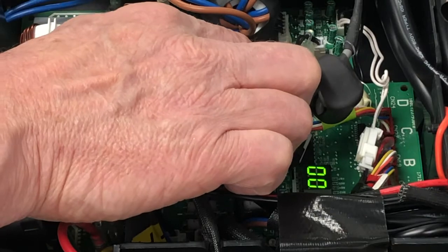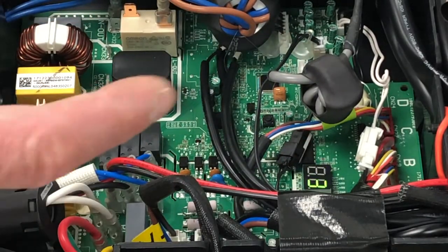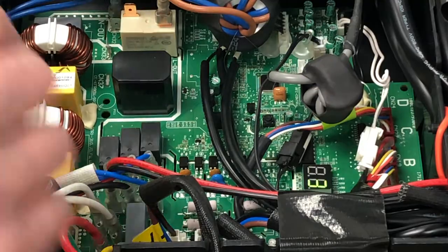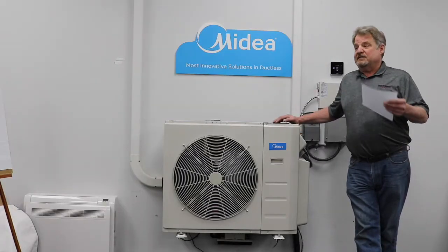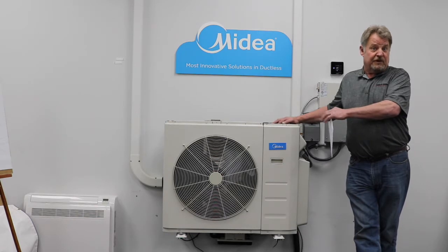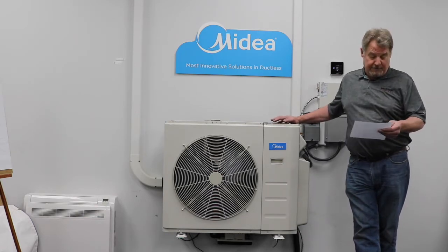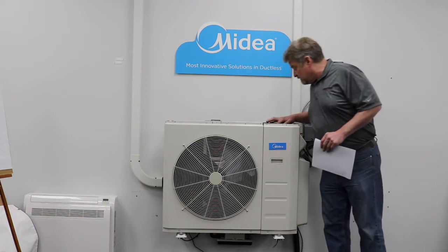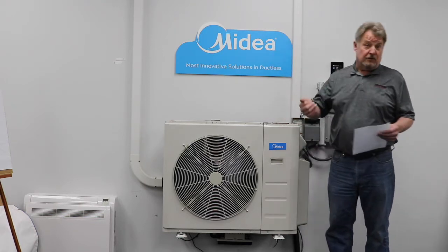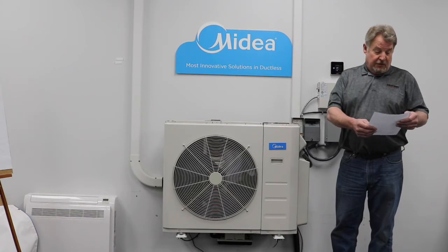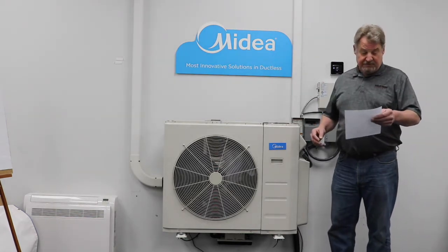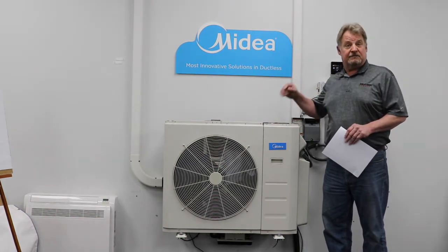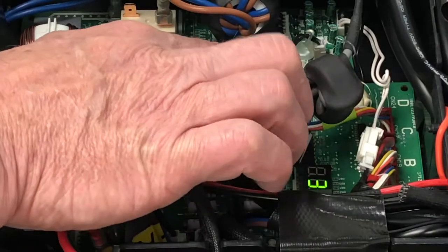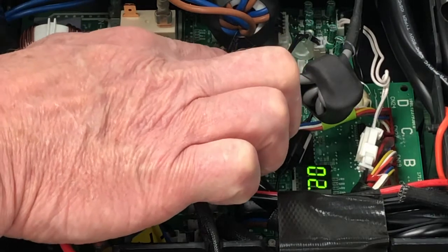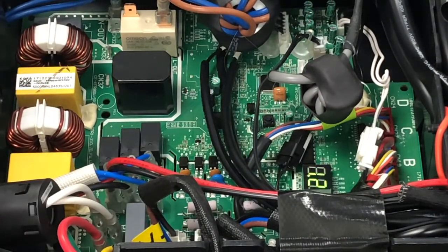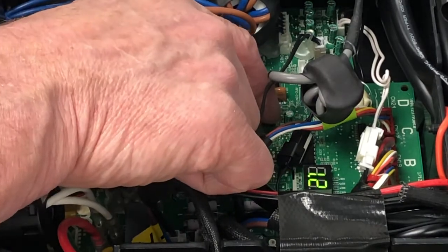It's going to come up and tell me the quantity of indoor units that are connected to this system. On this one it says 3 because I have 3 fan coils. Obviously for troubleshooting, if I had 4 and I only show 3 here, it means one of them is not communicating. The next thing, if I press it 2 times, it's going to tell me what mode the unit is in. Is it in cooling? Is it in heating? Is it in standby? 3 through 7 tells me what each indoor unit capacity is, starting with port A, port B. So if I press this 3 times, 1, 2, 3, it's going to tell me the capacity of the fan coil that's connected to port A, which happens to be over there.